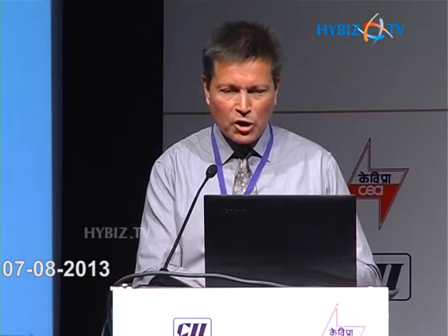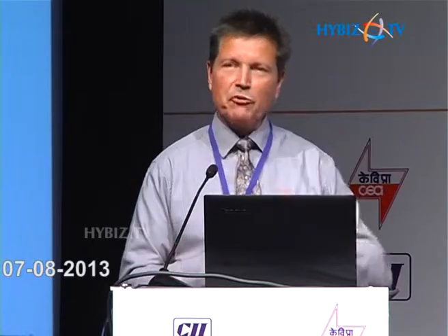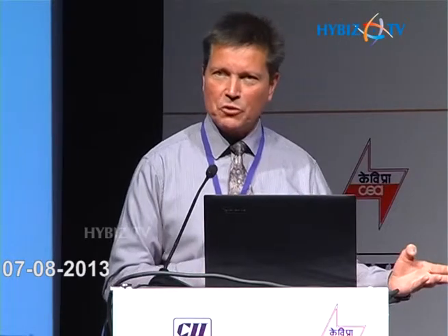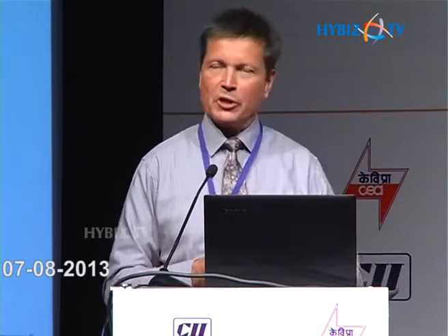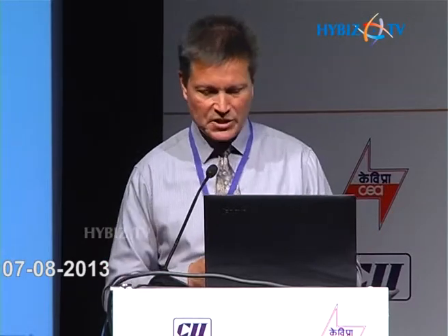And for that, we need a gas generator. We need that to generate that. Of course, to monitor all the other gas compounds, we cannot put them through the converter, as some compounds will actually change during the pass-through of the converter. So we just have a small switching valve, and we can bypass the converter when we monitor the normal gas compounds. And in this way, you have a complete solution for all gases.